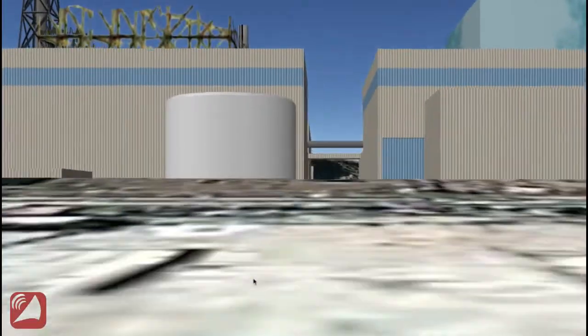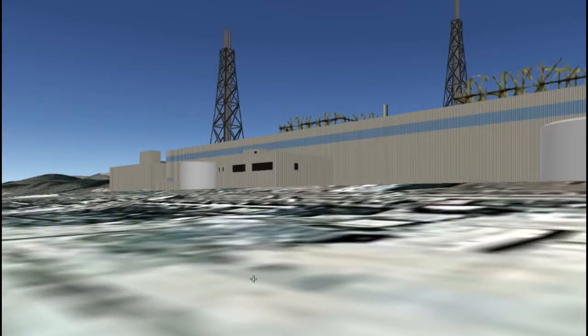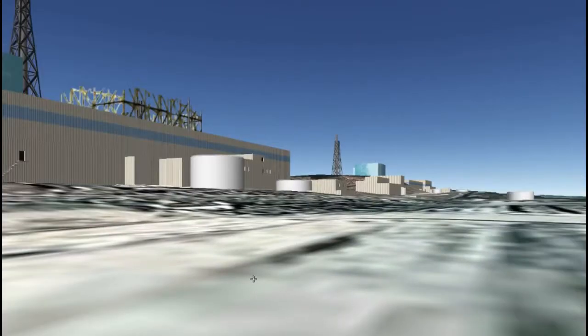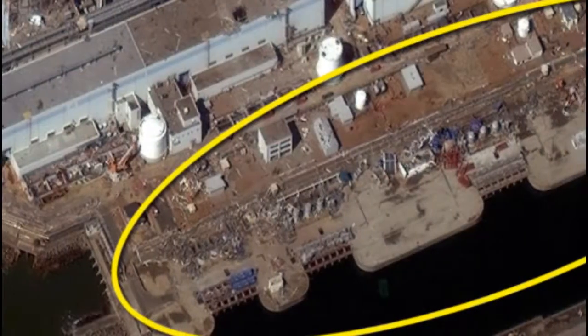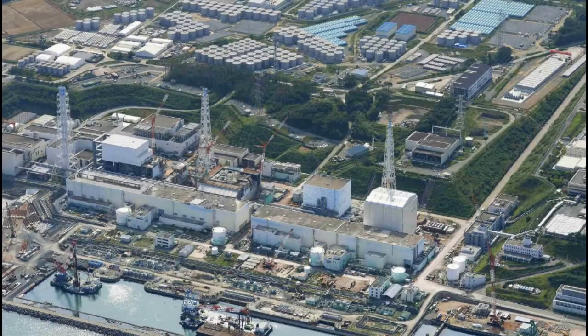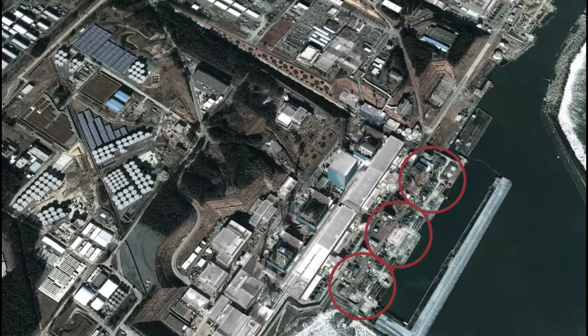Along the water there's a long row of turbine buildings. While impressive, there's not much going on inside them from a nuclear safety standpoint, though they do have basements flooded with radioactive waste. Beyond those is rubble along the waterline where the cooling pumps were — all of which failed as a result of the tsunami. Even if the diesel generators hadn't been flooded, they would have failed anyway because they could not have been cooled due to all that rubble along the coast.